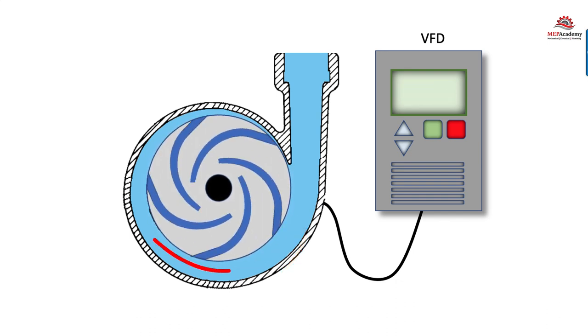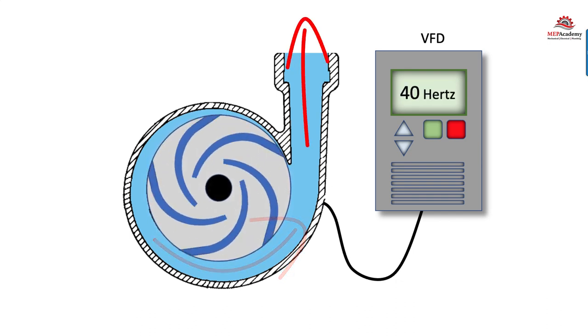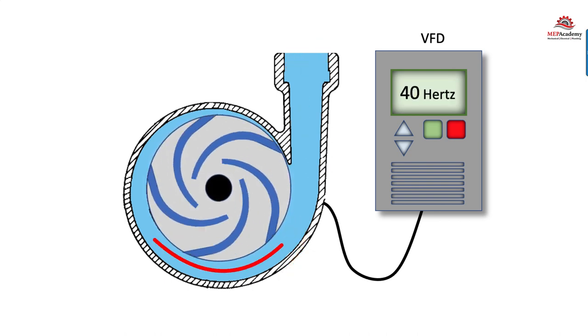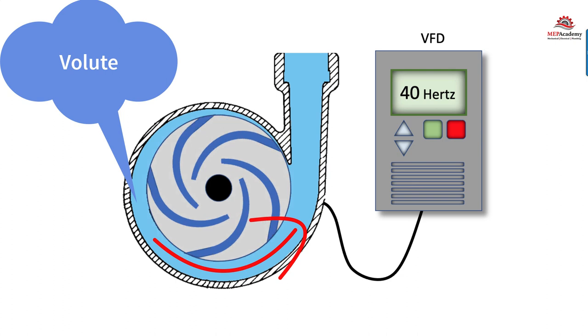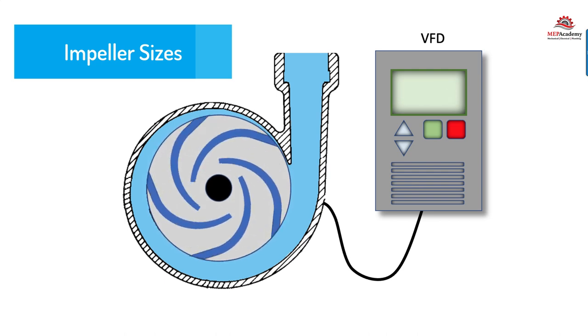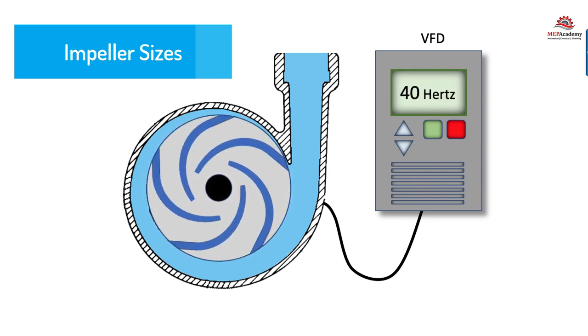The spinning vanes create a centrifugal force throwing the water from the rotating impeller. The water discharged by the impeller is thrown by centrifugal force into the spiral shaped volute, which is the housing surrounding the impeller. Pumps are available with various impeller sizes.